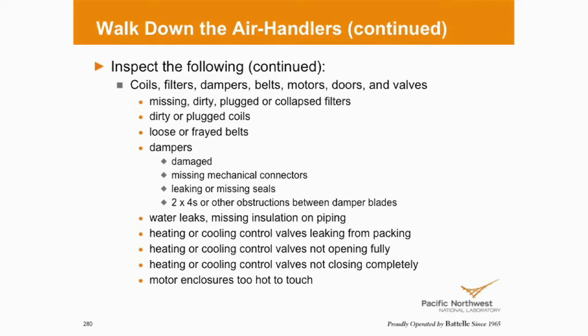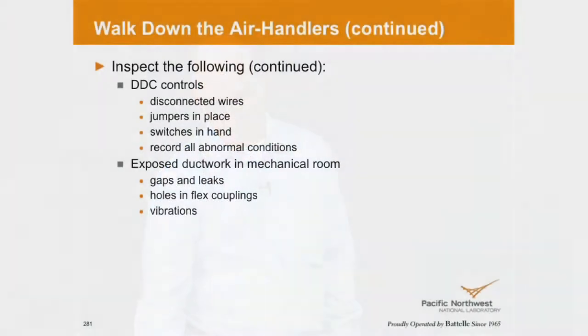Motor frames, enclosures, air-cooled motors, are they too hot to touch? You should be able to put your hand on a motor, hopefully, at least for a few seconds. With an infrared camera, if it's above 150, 160, unless it's rated for that, you might be looking at a problem down the road. Okay, the controls, BAS, DDC, whatever you want to call it. If I've got panels, do I see the wires have been disconnected? Maybe they've got hand-off-auto switches inside their panels. Some of them do. Are they in hand or are they in auto as well? Do I have jumpers in place? Ductwork, do I have gaps, leaks, flexible couplings that have come apart, vibrations?